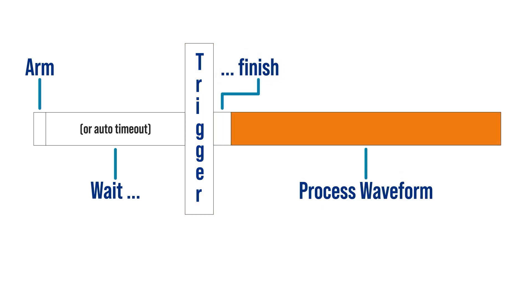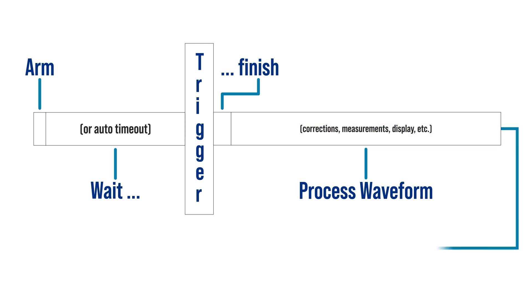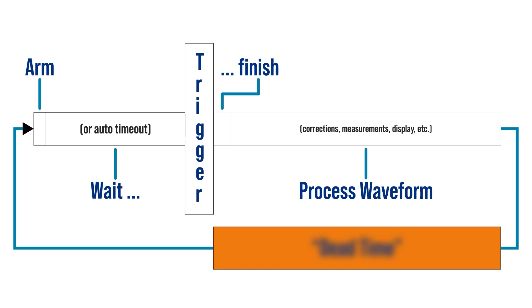Here's a timeline of how a scope acquisition works. The trigger arms itself and starts looking for the event. If Auto Mode is enabled, it times out after some amount of time. Once the trigger happens, the acquisition buffer continues filling. Then the data is transferred to a computer for processing and measurements and all the other fun scope stuff. Once all of that is done, the trigger circuit rearms itself. Now, the time from when the trigger happens until the scope can rearm, it isn't watching the signal anymore. We call that the acquisition dead time.